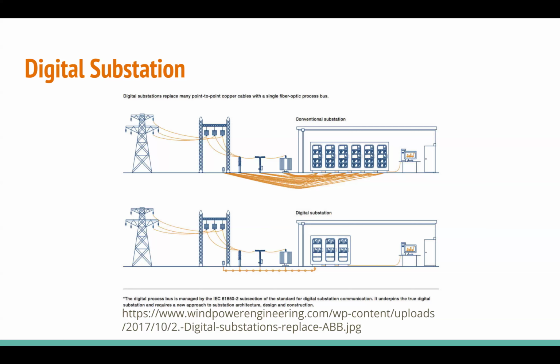Would that mean there would need to be protection grade metering devices out by the CTs in the yard? Yes. Those are called merging units and process interface units, depending on if you're working directly with the breakers and stuff. When we talk about signals in a second, I'll discuss that more. But yes, you still need to do the analog to digital conversion.